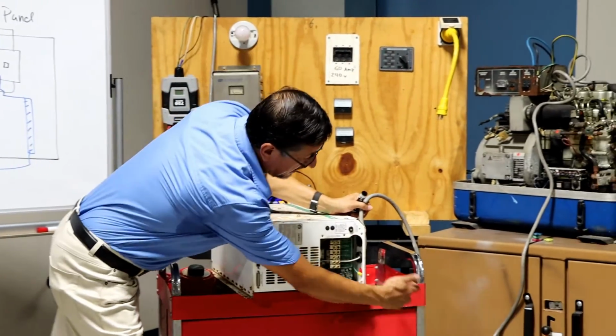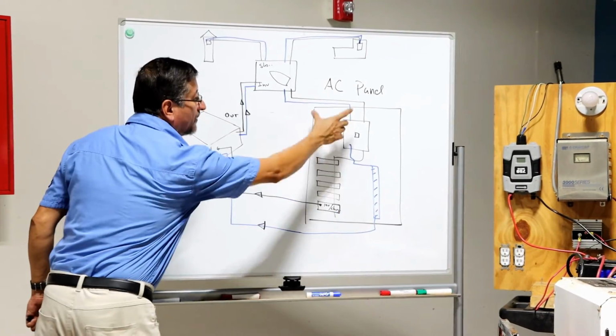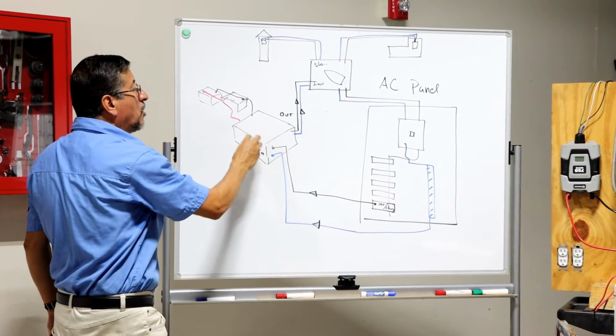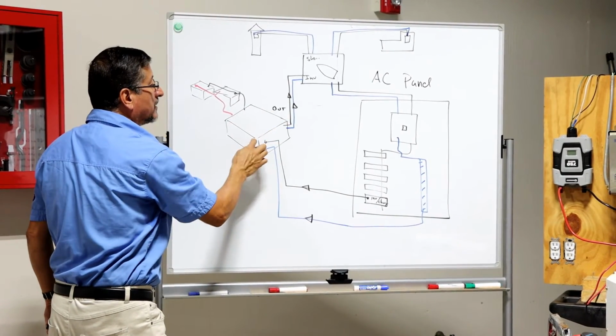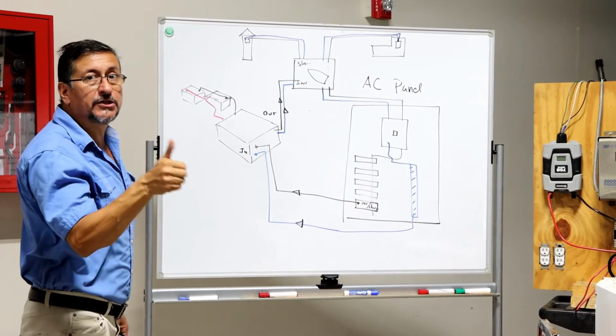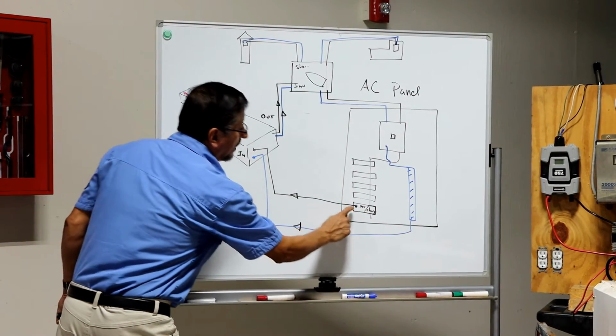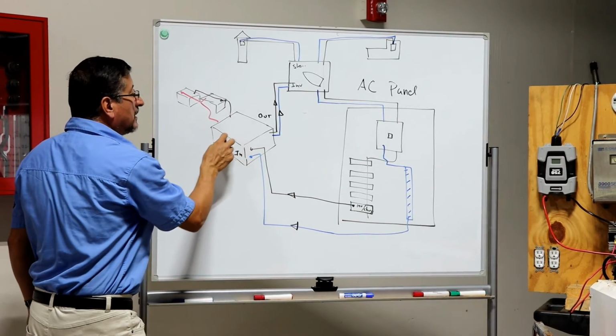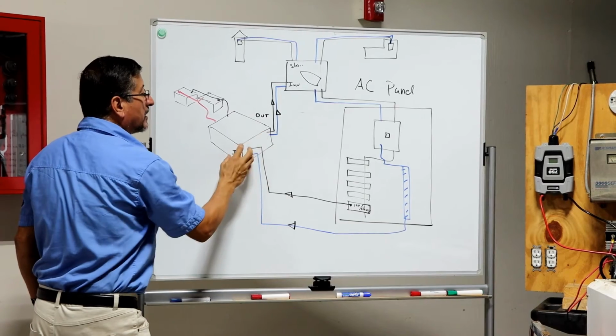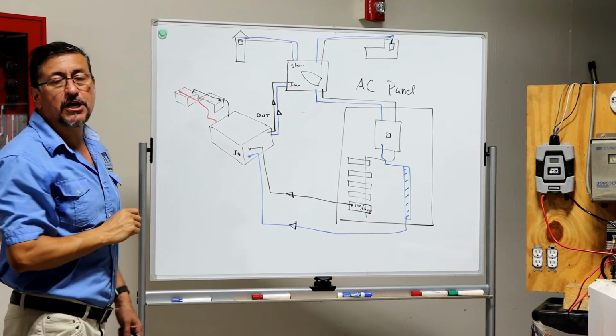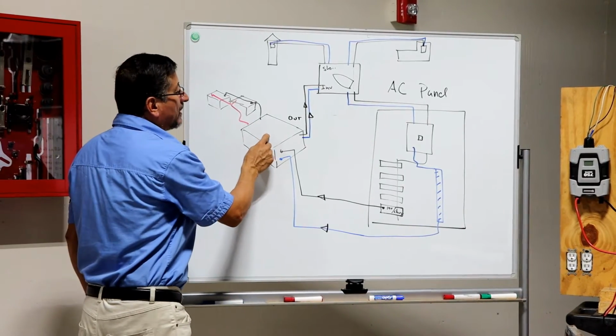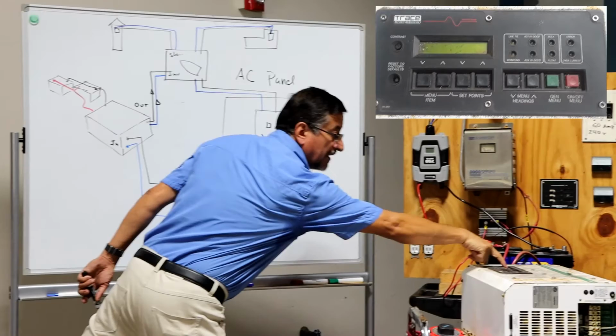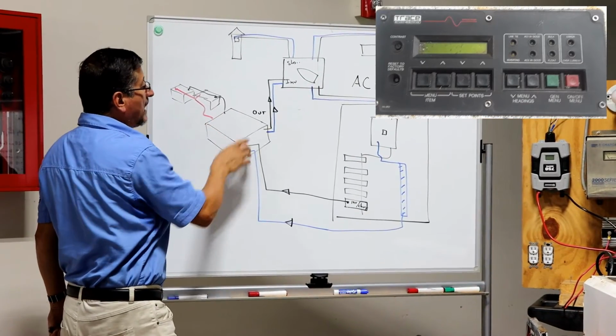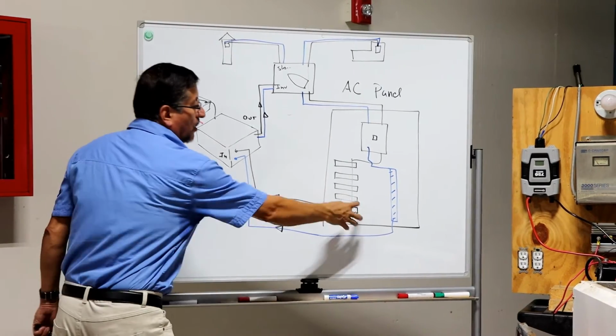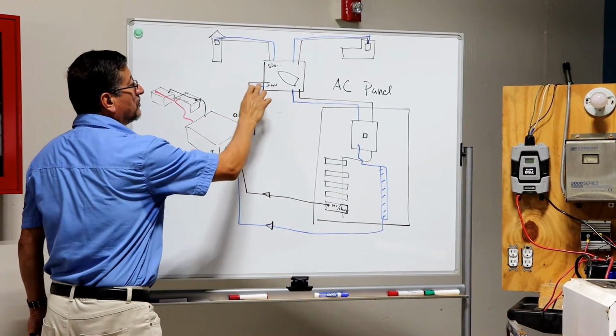And the input AC power is power coming from one breaker of the AC panel dedicated to activate the small battery charger located inside of the inverter, used to keep those batteries fully charged. That power coming from that breaker is only to activate the battery charger located in the inverter. When the inverter is running, when the inverter is activated on, the inverter is producing power and this input is closed. It does not receive power because in this moment the inverter is producing power.